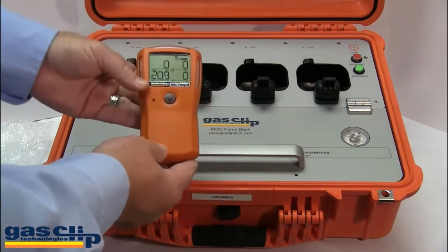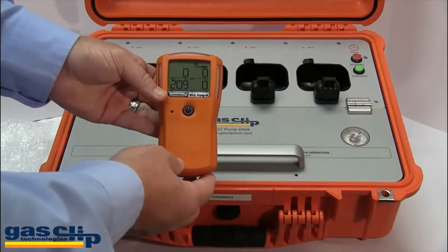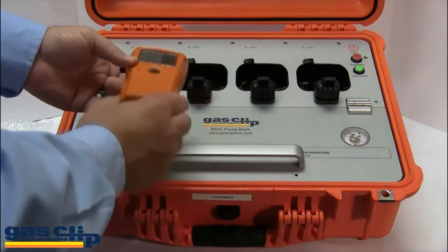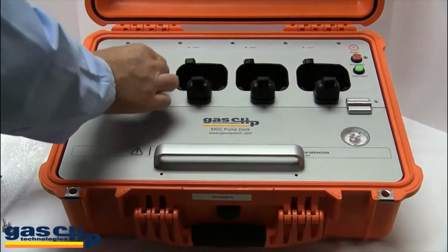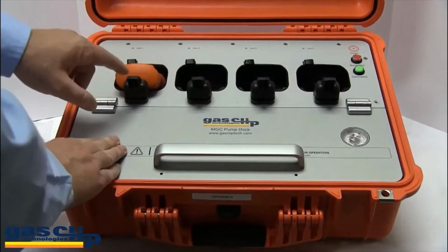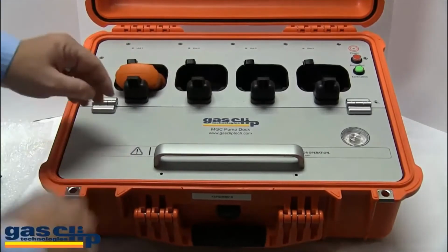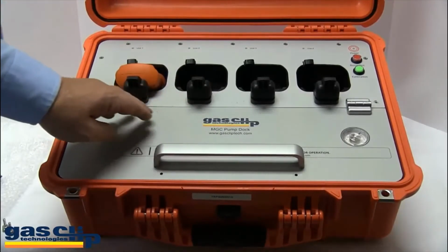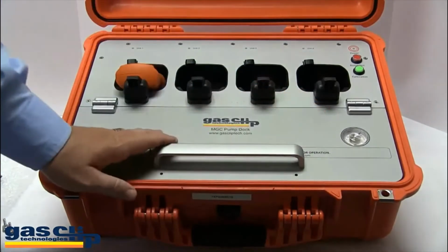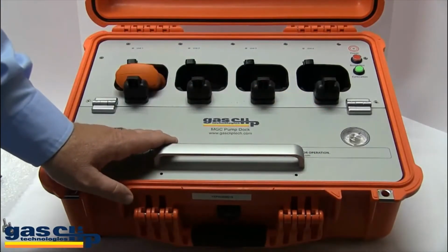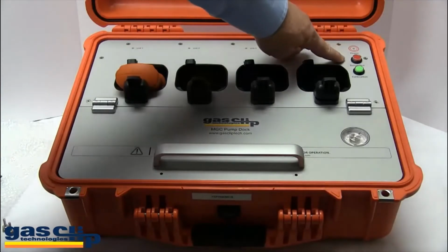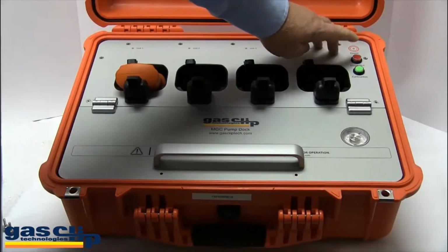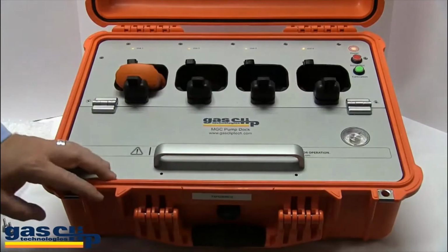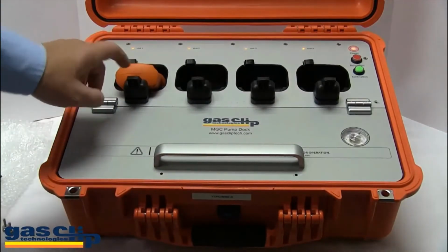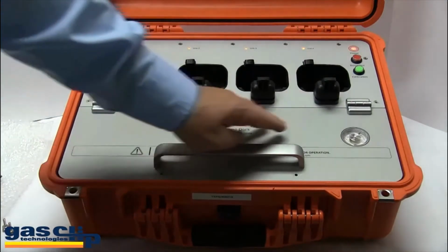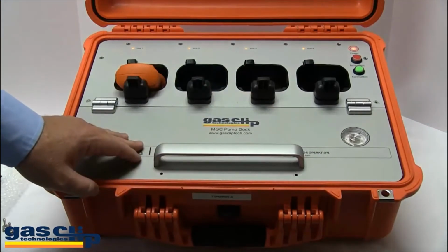To bump test your 4-gas Mgc pump monitor, all you have to do is slide it head down into the bay and press down, securing it underneath the latch. This docking station will bump test anywhere from 1 to 4 monitors at the same time. To perform a bump test, all you have to do is press the red button which corresponds with the bump test. You will hear one beep. That's because there's one monitor in the bay. If there were 4 monitors, you would hear 4 beeps.